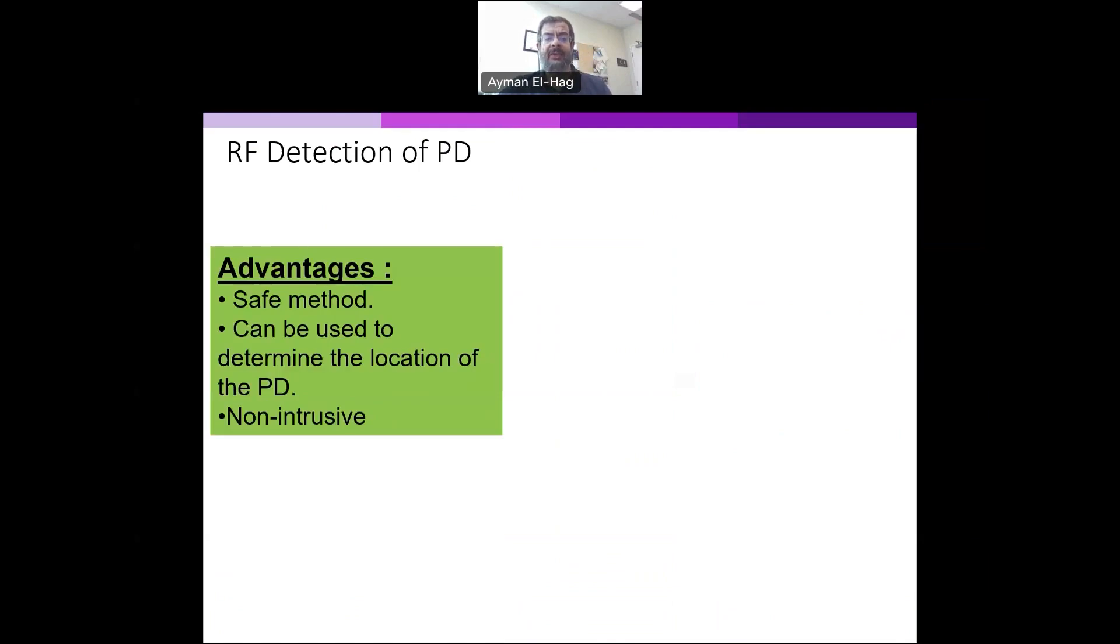Also, another advantage is it can be used to determine the location. If we use multiple antennas, because the partial discharge will arrive at these multiple antennas at different times, then we can localize the partial discharge location. And it's very non-intrusive.